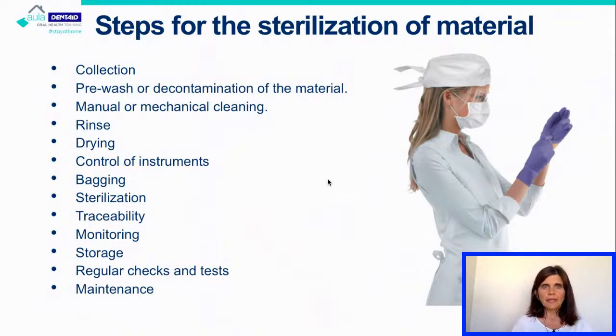For example, ultrasounds mean less time manipulating the instruments, and the perfect one is to use a thermodisinfector, where you go from the box with the material inside the cassette, and you put it inside, and it will process, clean and disinfect: thermodisinfection. Once it has finished, we will seal it and put it inside the autoclave. If not, we will follow with the rinse, the drying, and the control of the instruments.